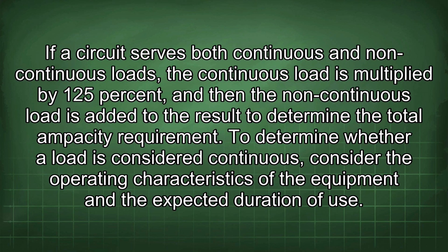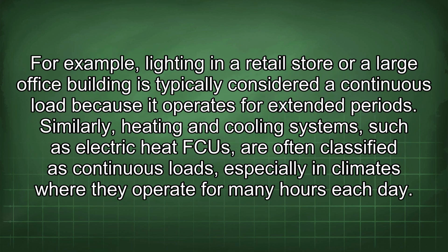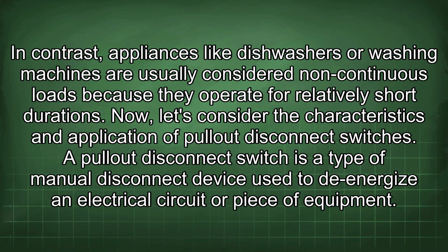To determine whether a load is considered continuous, consider the operating characteristics of the equipment and the expected duration of use. For example, lighting in a retail store or a large office building is typically considered a continuous load because it operates for extended periods. Similarly, heating and cooling systems, such as electric heat FCU, are often classified as continuous loads, especially in climates where they operate for many hours each day. In contrast, appliances like dishwashers or washing machines are usually considered non-continuous loads because they operate for relatively short durations.